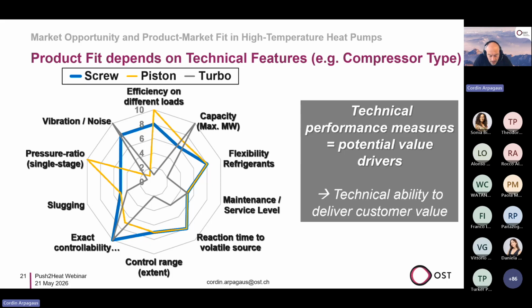When we overlay a piston compressor, this is probably more suited when the loads are varying often, so it's more efficient with variation of part load operation. The pressure ratios can also be higher with the piston compressors. Okay, it's always discussion here, but it just should illustrate that the thinking steps are to think which compressor technology fits best to the application, what are the attributes. The turbo compressors, we will see later, have the advantage of high capacity, so they can reach several 10 of megawatt heating capacity, for example. And so these technical performance factors are the potential value drivers, and this gives then customer value.